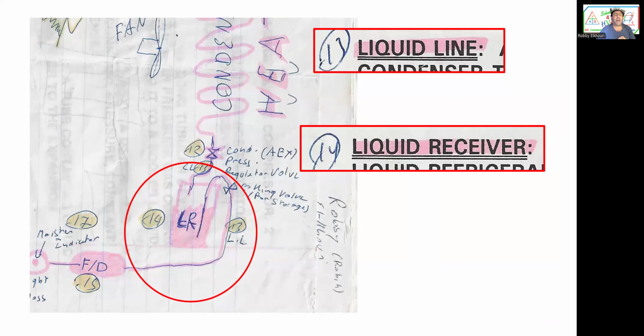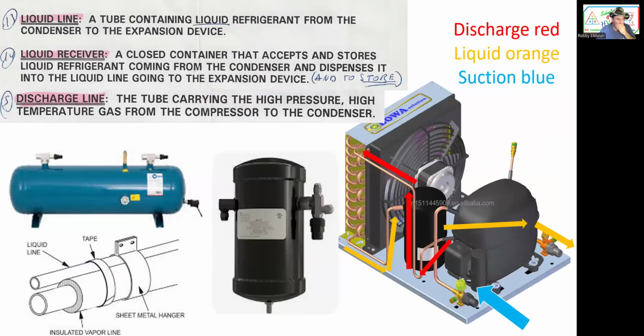Next, the liquid line and liquid receiver. The liquid receiver's job is to store refrigerant. Liquid receiver job and TXV go hand in hand. Liquid receiver is not needed on water-cooled equipment. Why? Because water temperature doesn't change much, maybe 2 or 3 degrees. Water temperature is always steady. Here in Florida, water is warm. But back home in California, water is always 55. Unless you're in Gilroy, water is 70. But so therefore, we don't need the liquid receiver.